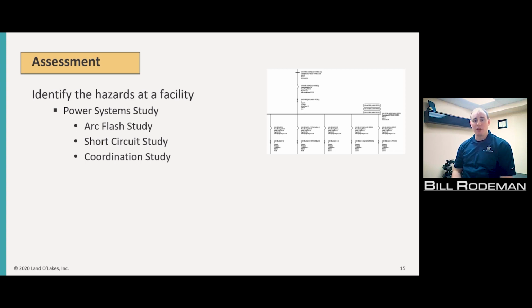Coordination study: if I have a fault occur at a piece of equipment, which breaker is actually going to trip first to stop it? You really want the one directly upstream to trip. If I'm working inside a motor control center and a fault happens, I want the main feeding that motor control center to trip, not the main feeding the building. You want to shut off as little as possible, so that would be identified during the coordination study.